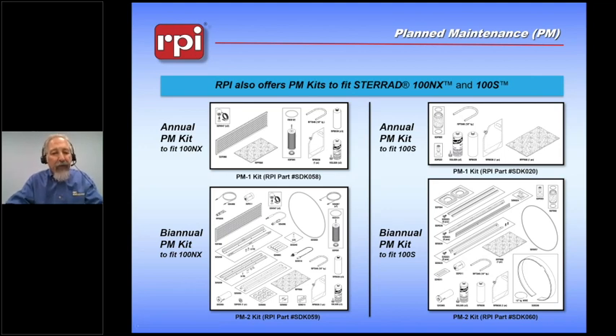Now, the 100S does deliver its hydrogen peroxide very differently. It does not have a vaporizer condenser assembly. It takes the hydrogen peroxide directly at 59% and transfers it into the chamber directly at 59% and manipulates it from there. There are also rails and a catalytic converter that need to be replaced on a yearly basis.